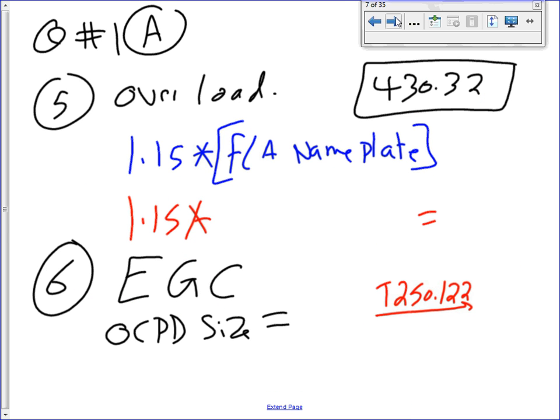Overload. The overload, guys, I told you from 430.32, overload is always the full load amp on the nameplate. Now you will ask me, Chad, well, you didn't give us the full load amp, right? I didn't give you the full load amp. So that's when I stick a 50 amp here, and I'm going to call this given. Did I give you the full load amp of these motors? Oops, I better give you the full load amp of these motors. Okay, overload size for 10 horsepower. So I will give you guys the full load. This is 50.